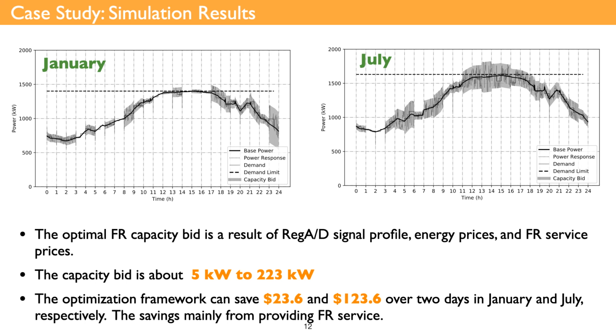The solid line shows the baseline without providing FR, and the shadow around the baseline is the capacity bids that we calculated from the optimal control framework. We can see the FR capacity bid actually varies at different hours. This is showing us that the capacity bid is a result of regulation signal, energy price, and regulation price. The capacity bid varies from 5 kilowatts to 223 kilowatts at different times. The optimization framework can give us an economic saving of $23 and $123 over 2 days in January and July, respectively. The savings are mainly from providing frequency regulation service.